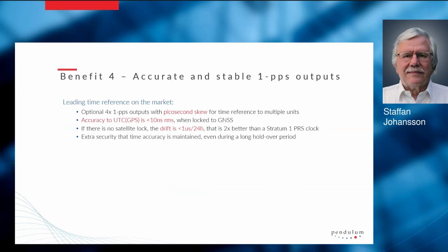And benefit number 4, we have a very accurate and stable 1 PPS output. The optional extra 4 1 PPS outputs have been trimmed to have a minimal skew between the outputs, down to a few picoseconds, to be used for time reference to multiple units where you want to have exactly the same time relationship for all these units, up to 4 units. We have an accuracy to UTC that is less than 10 nanoseconds, which is better than the typical standard, which is normally specified to be between 20 or 30 nanoseconds RMS.